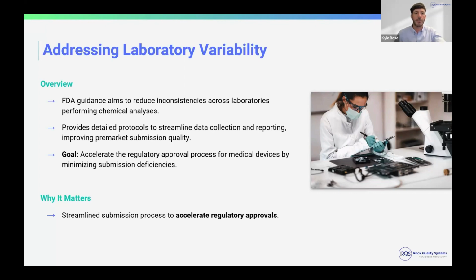The goal from the FDA is to accelerate the regulatory approval process for these devices and to minimize any deficiencies with the submission review and really accelerate regulatory approval. So this guidance applies both to actual manufacturers, as well as the testing labs that might be doing this testing. As I said earlier, it's unlikely you'll be doing this testing in-house. Even if you have a full analytical chemistry lab, I still think most of this will be done externally.